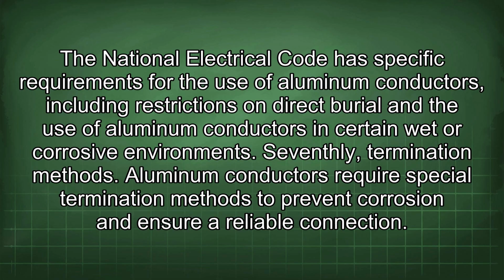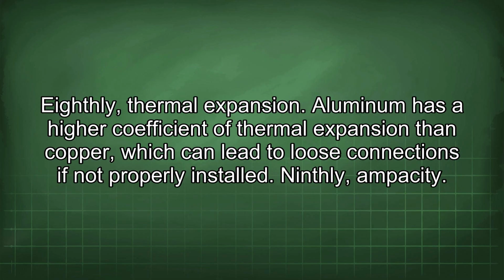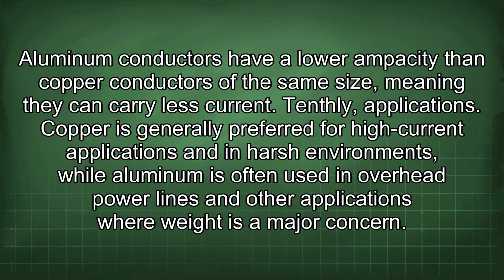Seventhly, termination methods. Aluminum conductors require special termination methods to prevent corrosion and ensure a reliable connection. Eighthly, thermal expansion. Aluminum has a higher coefficient of thermal expansion than copper, which can lead to loose connections if not properly installed. Ninthly, ampacity. Aluminum conductors have a lower ampacity than copper conductors of the same size, meaning they can carry less current.